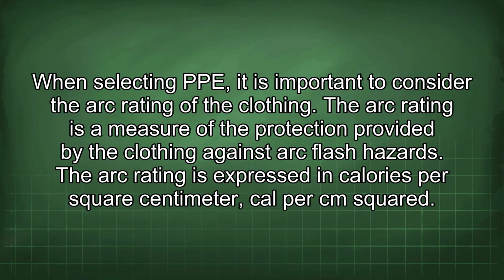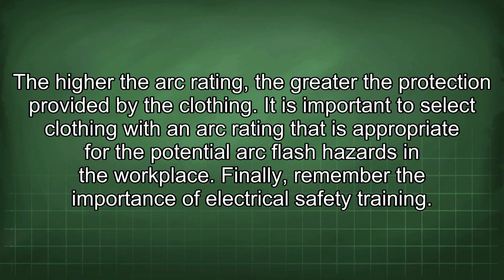When selecting PPE, it is important to consider the arc rating of the clothing. The arc rating is a measure of the protection provided by the clothing against arc flash hazards. The arc rating is expressed in calories per square centimeter, cal per cm squared. The higher the arc rating, the greater the protection provided by the clothing. It is important to select clothing with an arc rating that is appropriate for the potential arc flash hazards in the workplace. Finally, remember the importance of electrical safety training.